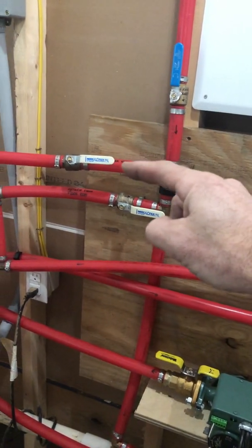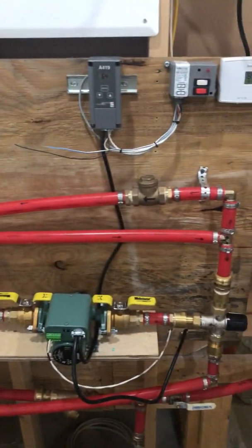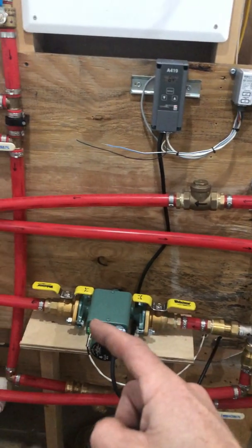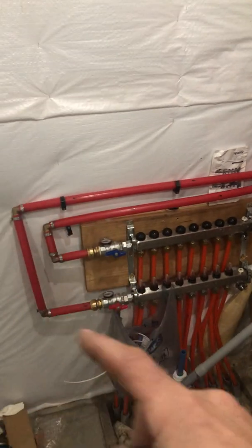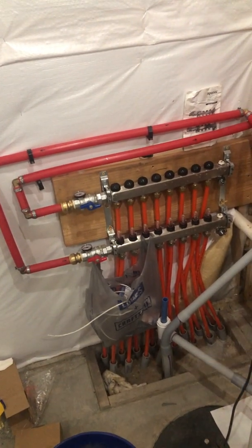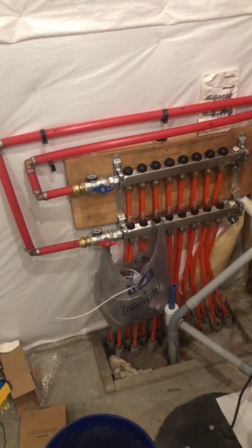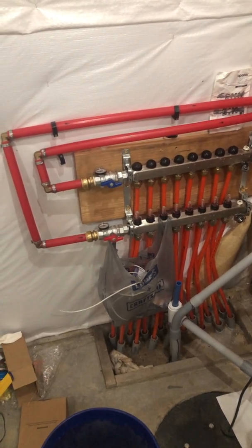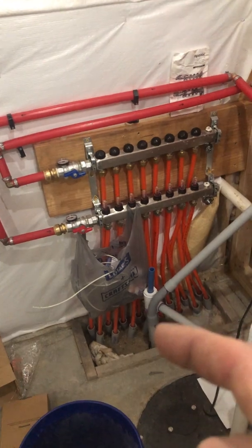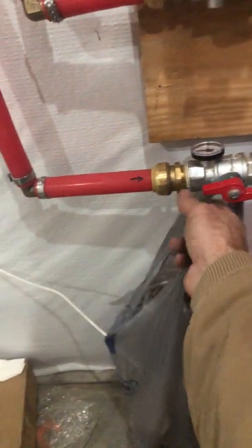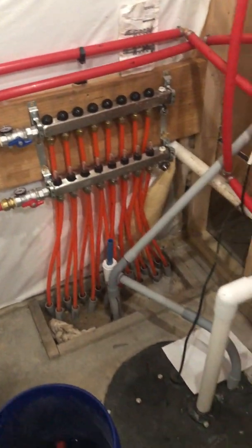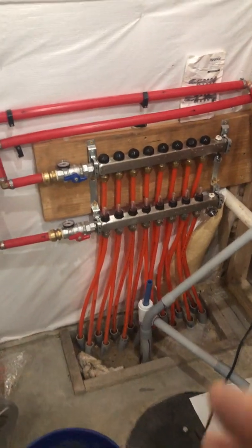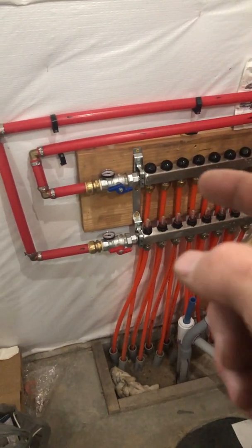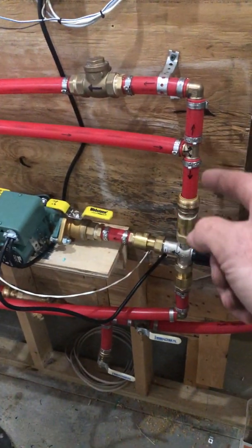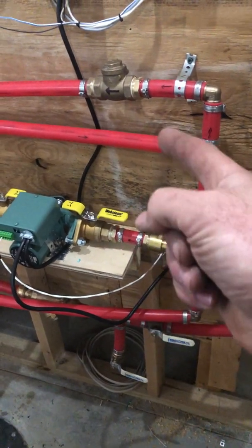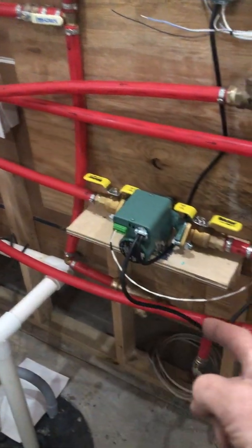And some is going to get drawn in by a secondary pump that goes down and around into a mixing valve here, and then this pump is pushing water over into my in-floor heating. Now, before the house was built, I did a vapor barrier. I added 2-inch polystyrene foam and hog wire mesh, and I put these 8 loops that you can see going down here. I put these 8 loops 1 foot apart, and all of my zones are between 140 and 180 feet. So it flows through the floor, comes back out, and then some of the water is going, the mixing valve is going to recycle some of the cold water, and then some of it gets cycled back, and it goes back into the system.